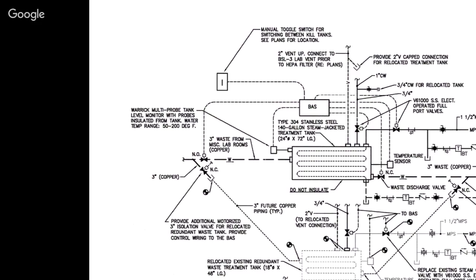The process is the waste comes from the sinks into the tank. We have a motorized isolation valve here on the inlet, and a motorized isolation valve on the outlet. We have a steam system that comes in and feeds a coil, and the condensate goes out. This is all controlled through the general building automation system that the controls contractor used for all the HVAC controls. When the level sensor measured that it was high enough, it would close the inlet valve and then send a signal up to the researchers in the lab, a red light saying, tank's full, stop what you're doing.